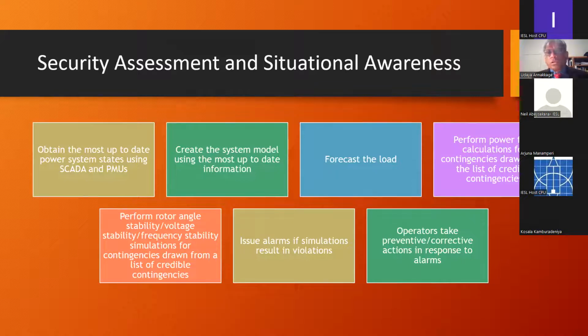You also need to forecast the load. And we are not talking about forecasting load for next month, next week, next year. We are talking about forecasting the load over a short time. And I already mentioned 15 minutes. So in that context, what I mean is to forecast what the load is going to be 15 minutes from now. Then for that forecasted load, perform power flow calculations for contingencies drawn from the list of credible contingencies. And if you're happy with that, then we do rotor angle stability, voltage stability, and frequency stability simulations for the contingencies drawn from the list of credible contingencies.